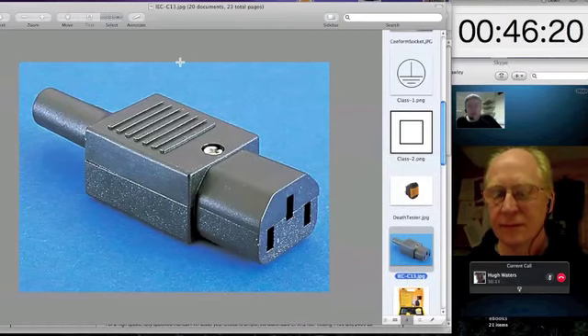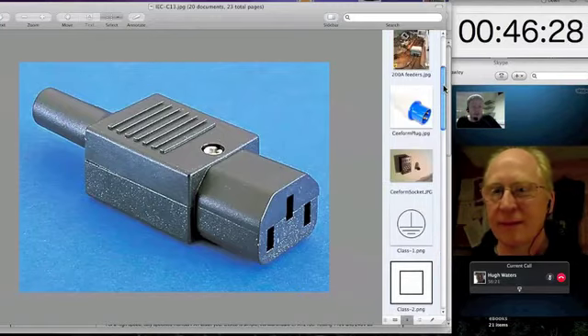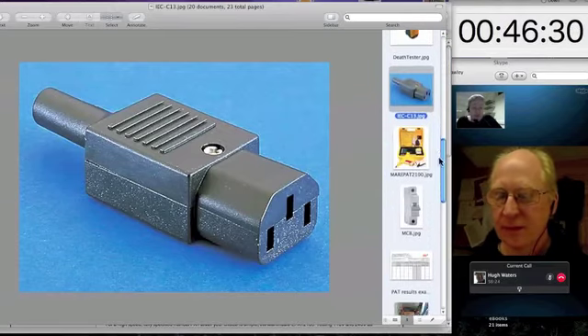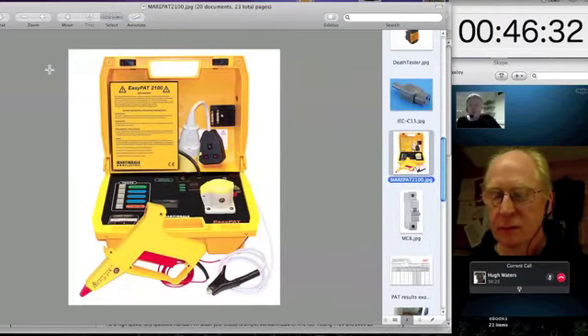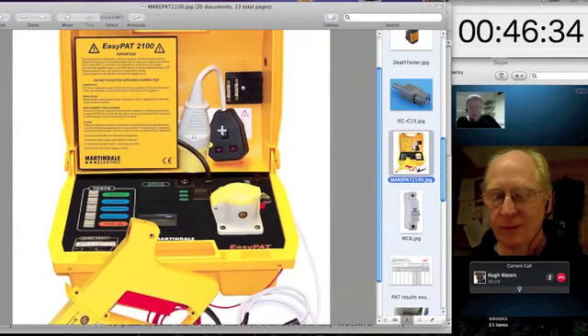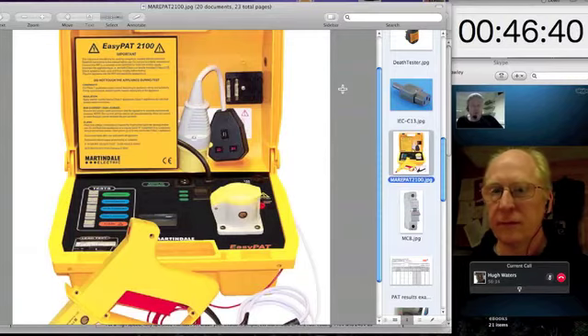But getting back to facilities with the way you do the cabinets, that's very, very typical to have that, and that would be the demarcation point where you would expect the installing engineer who's checking that this equipment cabinet is wired safely and there are no problems in it. That's the point where you'd expect him to interrupt the supply with his PAT tester and start doing his testing upstream of that 16 amp connector, through the cabinet, through all the circuits within the cabinet.